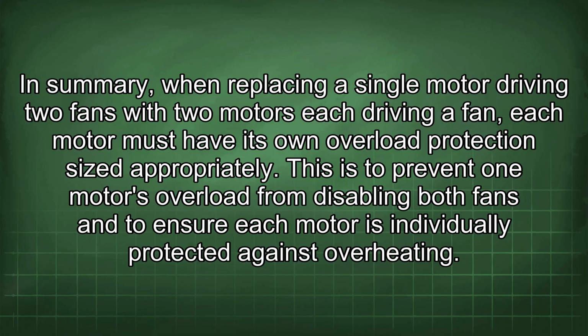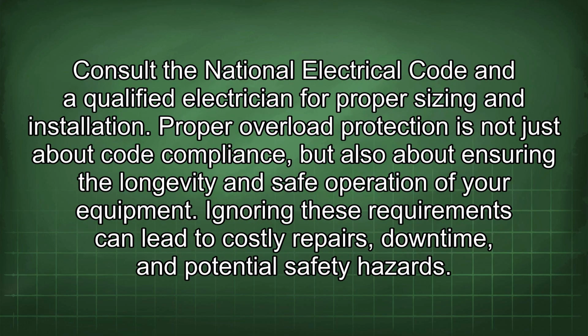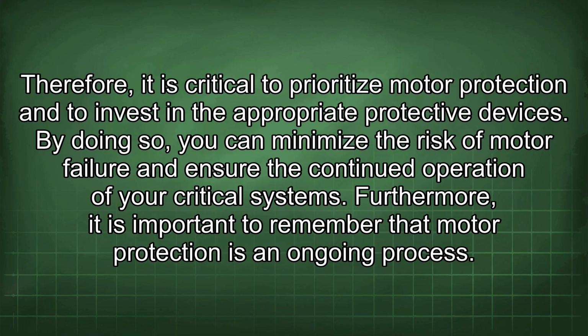This is to prevent one motor's overload from disabling both fans and to ensure each motor is individually protected against overheating. Consult the National Electrical Code and a qualified electrician for proper sizing and installation. Proper overload protection is not just about code compliance, but also about ensuring the longevity and safe operation of your equipment. Ignoring these requirements can lead to costly repairs, downtime, and potential safety hazards. Therefore, it is critical to prioritize motor protection and to invest in the appropriate protective devices.